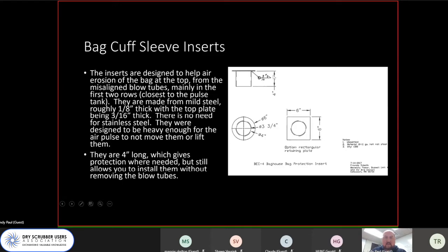Some things we've done to combat that: this is a sketch, but we've created a sleeve, used mainly in those first two rows. It's about a 4-inch total length and inserts right into the bag. It helps minimize the movement between the bag and the snap ring. We've seen it doesn't affect bag performance or cause degradation, and we were able to make them out of mild steel, no special stainless needed, making sure they were heavy enough that they didn't move around when the pulsing went off. This has been a very valuable tool for us, helping eliminate or slow down degradation, especially within those first two rows.